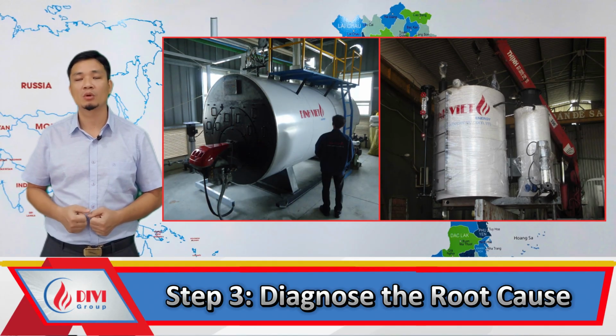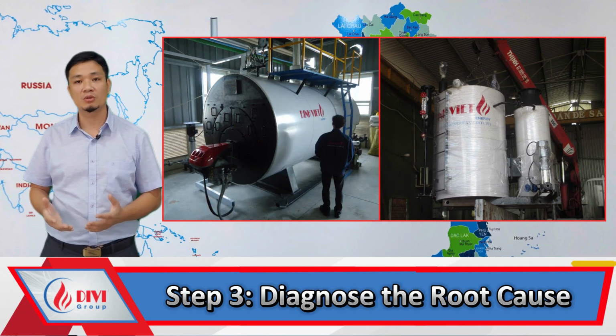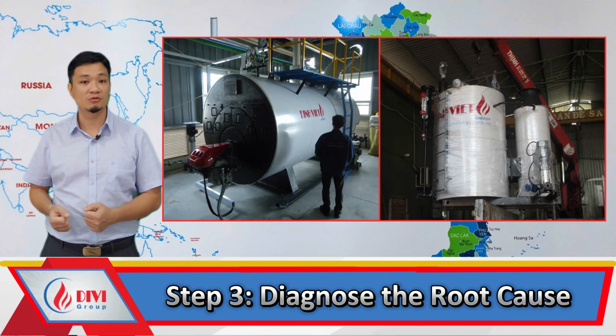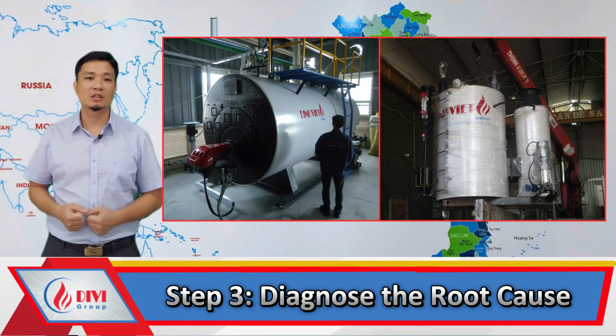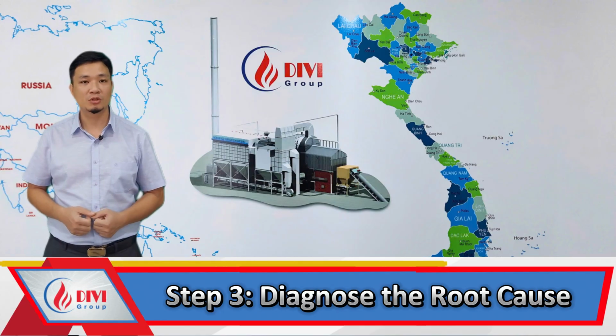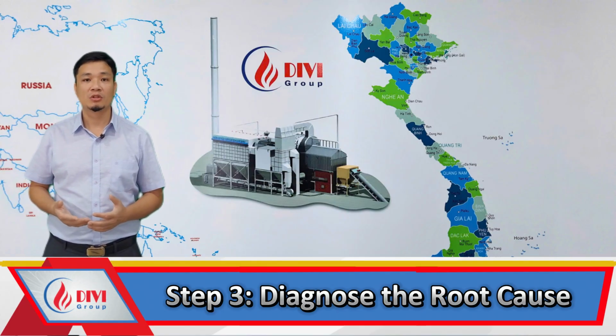In the case of oil-fired or gas-fired boilers that do not have an ID fan, you can fully open all inspection and access doors to allow natural cooling, then proceed with the internal inspection.